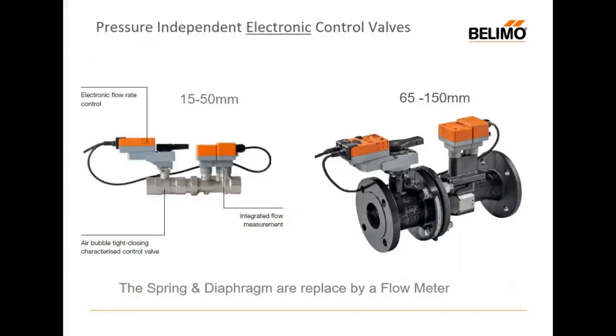So now, having talked about mechanical valves, I want to touch on electronic. Electronic valves don't use a spring and a diaphragm. We've replaced the spring and the diaphragm by a flow meter. The ultrasonic flow meter here is measuring the flow and telling the actuator what the real measured flow is. And the actuator is programmed with the design value. There's an algorithm in here which determines, am I above the design flow? If I am, automatically I'm going to limit the flow so I don't saturate this coil. And if I'm below the design and I've got 10 volts, I'm going to open up. Because the whole purpose of this valve is to maintain a balance and be able to control.